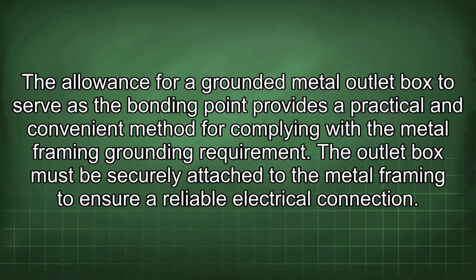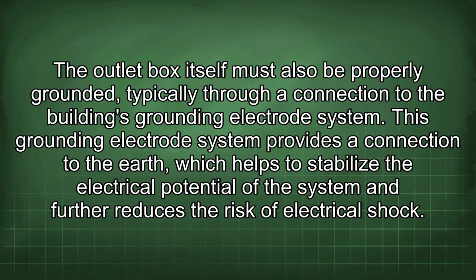The allowance for a grounded metal outlet box to serve as the bonding point provides a practical and convenient method for complying with the metal framing grounding requirement. The outlet box must be securely attached to the metal framing to ensure a reliable electrical connection. The outlet box itself must also be properly grounded, typically through a connection to the building's grounding electrode system. This grounding electrode system provides a connection to the earth, which helps to stabilize the electrical potential of the system and further reduces the risk of electrical shock.